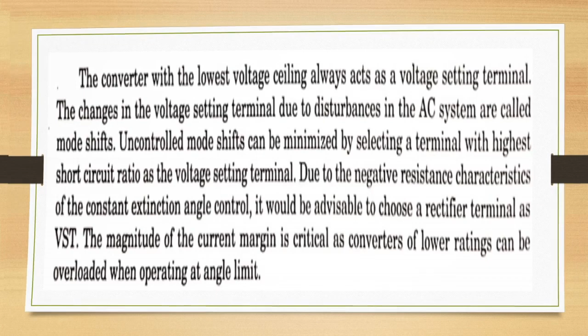Converter with lowest voltage ceiling always acts as a voltage setting terminal. Changes in the voltage setting terminal due to disturbances in the AC system are called mode shifts. Uncontrolled mode shifts can be minimized by selecting a terminal with higher short circuit ratio as a voltage setting terminal. Due to the negative resistance characteristics of the constant extinction angle control, it would be advisable to choose a rectifier terminal as VST. Magnitude of current margin is critical as converters of lower ratings can be overloaded when operating at angle limit.